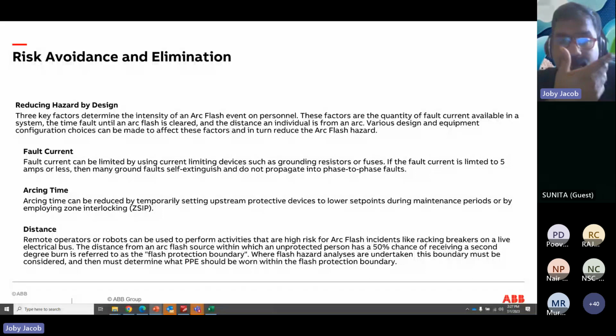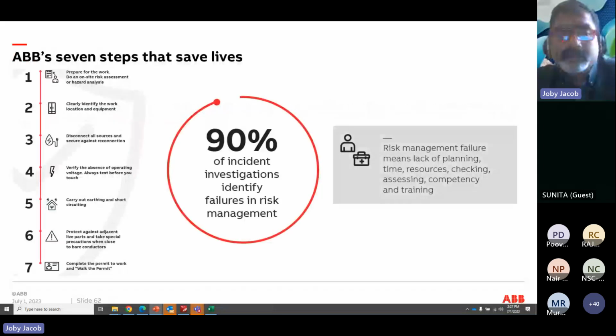Then the distance remote operations can be used. Nowadays, it's also used: rack in, rack out breaker mechanisms are there, so that the operative doesn't need to be too close to the panel actually. Yeah. We have a methodology called ABB 7 steps that saves lives.